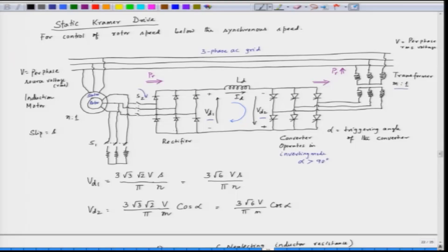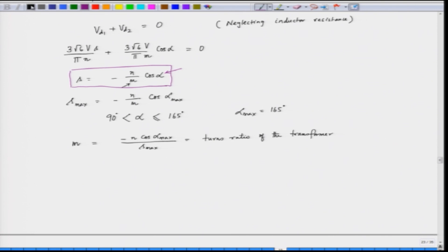The static Kramer drive looks like this. We have a rectifier in the rotor circuit, then we are recovering this power P_r and feeding this power back to the supply. The slip can be controlled by controlling the triggering angle alpha of the converter.